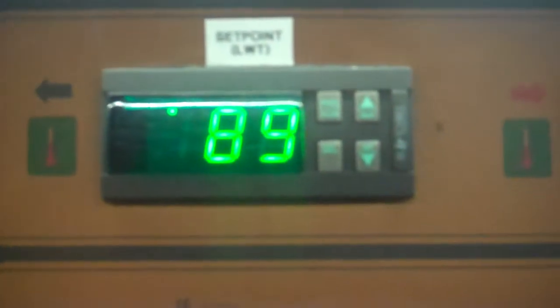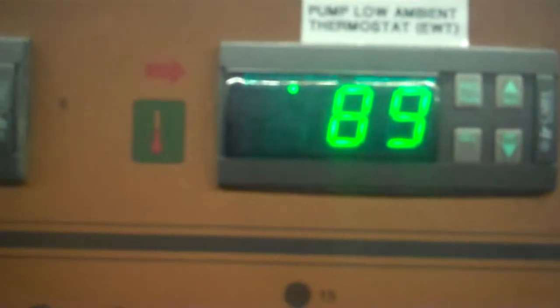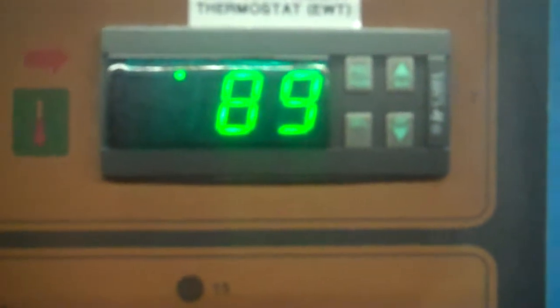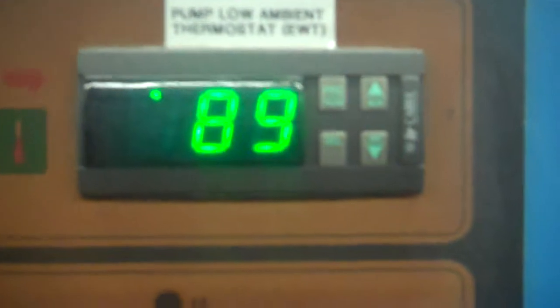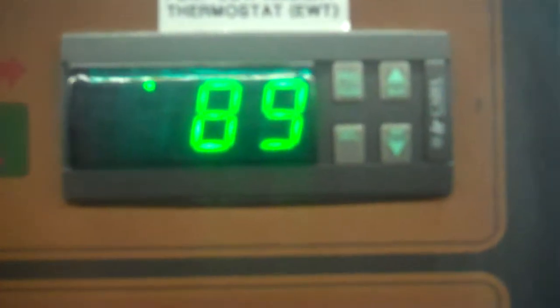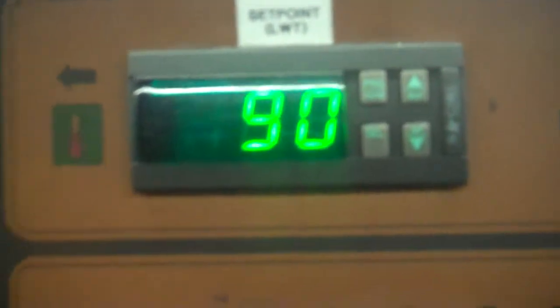Right now there's a little delay. There is a delay in the compressor turning on, starting to chill. That's built in. This temperature controller is the set point for the leaving water temperature, the primary set point. This one here you really shouldn't have to touch. This is a pump low ambient thermostat. It's detecting the entering water temperature, but this basically will keep the pump going in the event that it gets too cold outside. This is going to a southern location. You really shouldn't have to touch that at all. This is really the main thing you're going to be dealing with while you're operating the chiller.